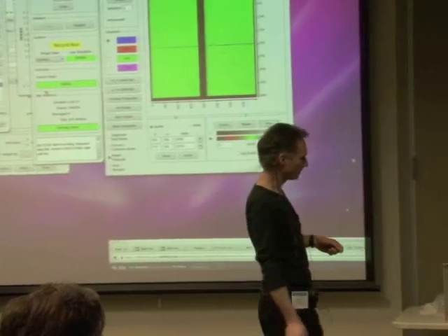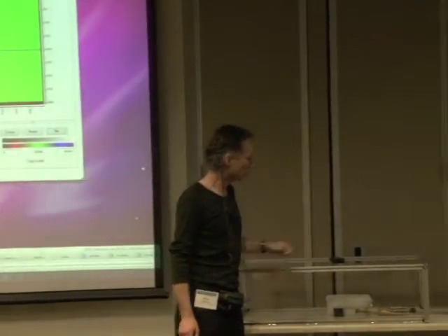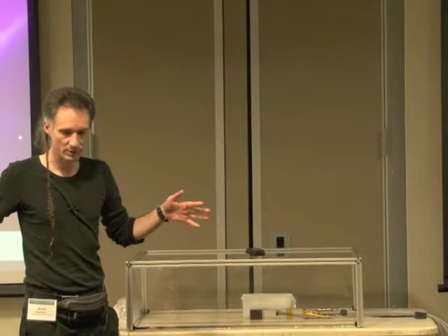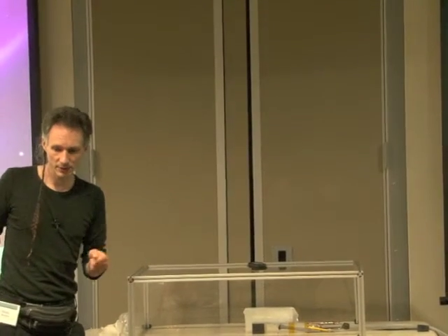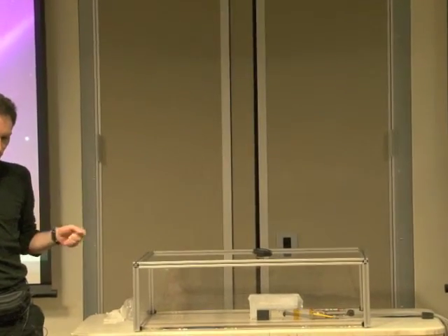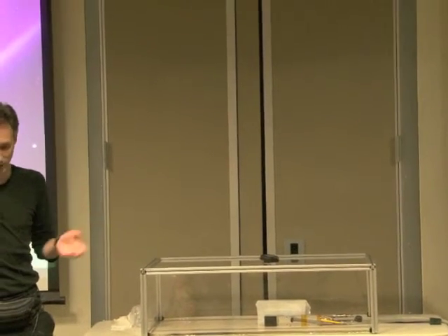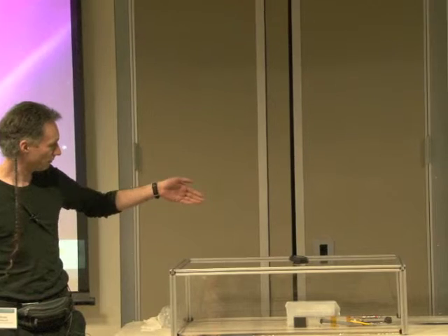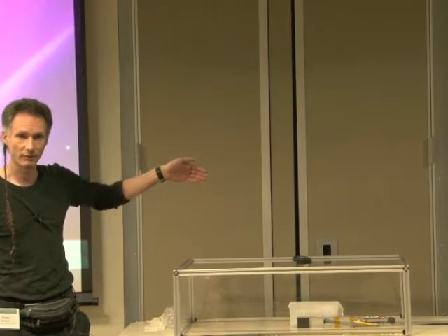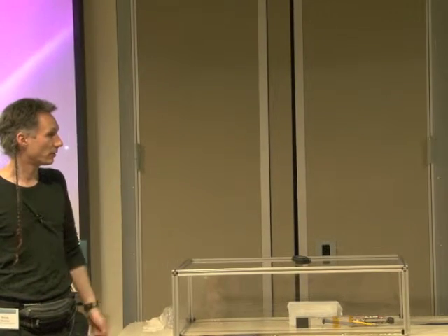This is a detector, the 140K CSPAD. In order to operate it here and show something, one uses very long integration times, 8 milliseconds. That means that for 8 milliseconds, it will collect lots of leakage current, and therefore we have to cool it. To cool it, we use a combination of a Peltier cooler with water. And in order to prevent condensation, we need nitrogen to purge it.